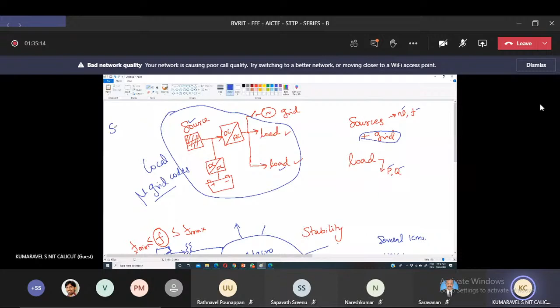Whatever we do in the macro grid, we follow the same process in the microgrid. Source is always a source, whether it's 10 kilowatts or 10 megawatts - there's no difference, because we have to regulate voltage and frequency. Source and load vary in their own way, so the total local system should be treated as a grid, and that grid is called a microgrid.